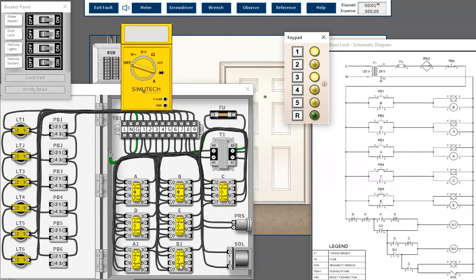All right. So the next one, of course, is 4, but it doesn't matter. If I can't get B2 here, 4 turns on C, which turns on the solenoid. But if we can't get B2 on, guess what? It doesn't seal in here, right? And we can't turn on the solenoid. So I know right now that it's B2, or something to do with B2.